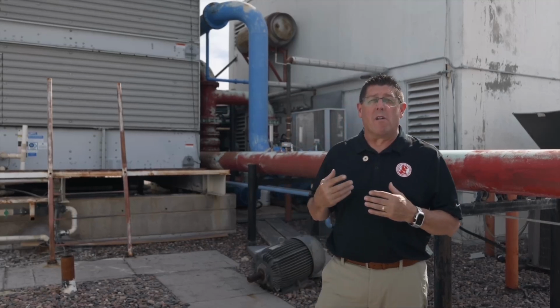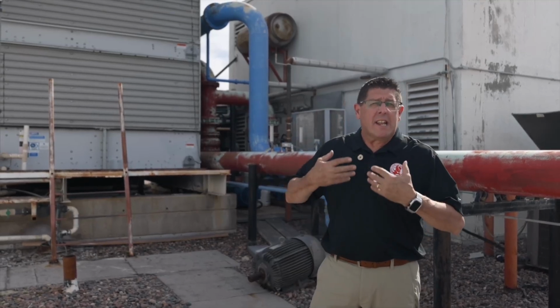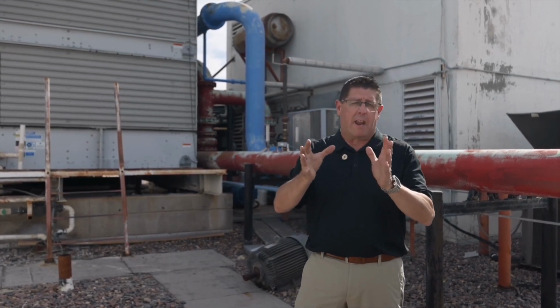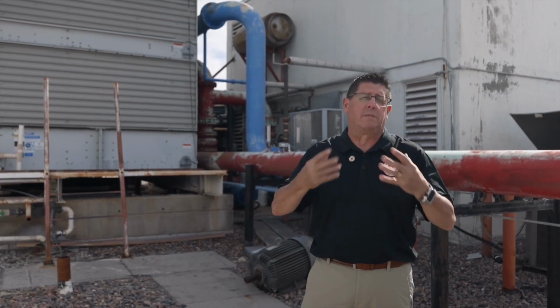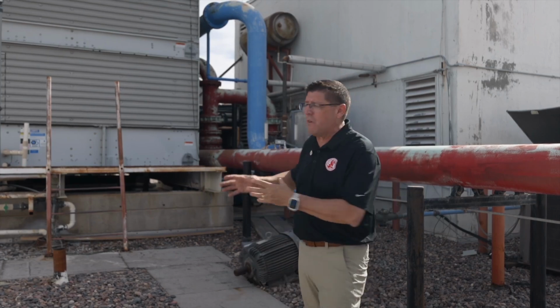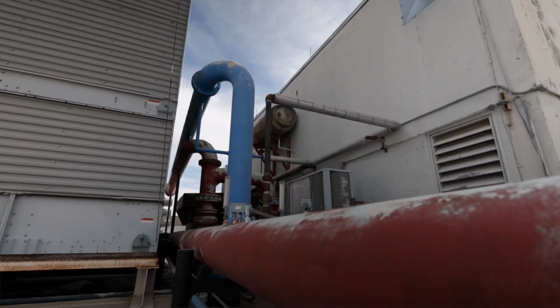This is our cooling tower. And once again, it is being used to move heat from the inside of the building to the outside of the building. It's taking large drops of water, making them small drops of water, and we're expelling the heat. We have a water temperature difference of about 10 degrees between the water going into the tower and out of the tower. And so when you look behind me, I've got a series of very large diameter pipes.